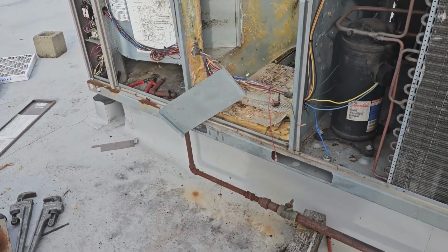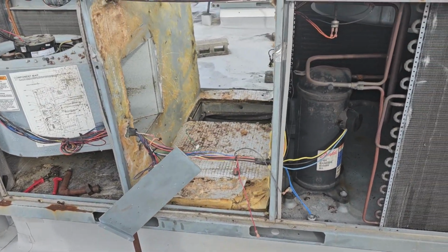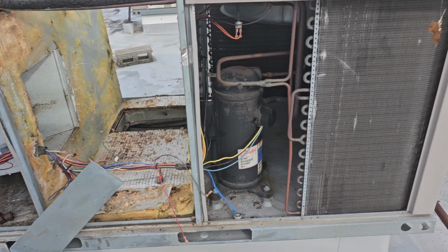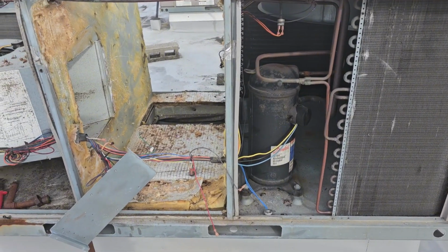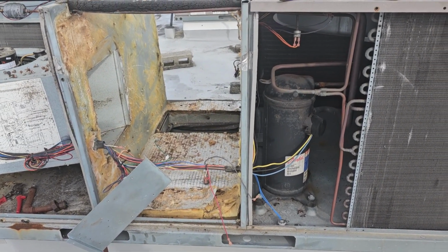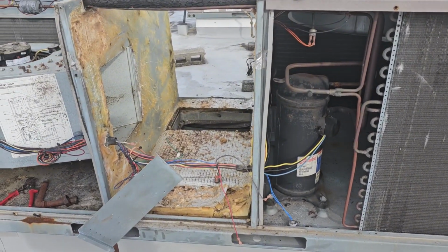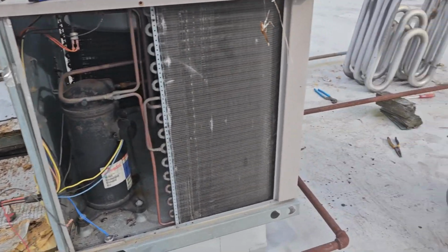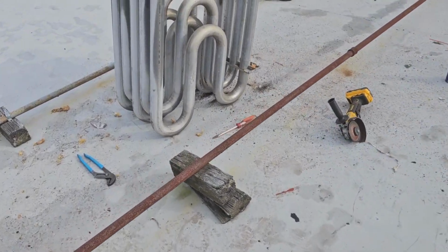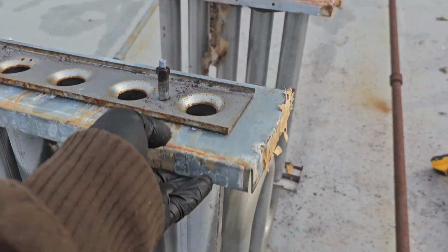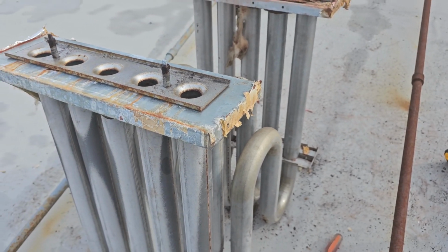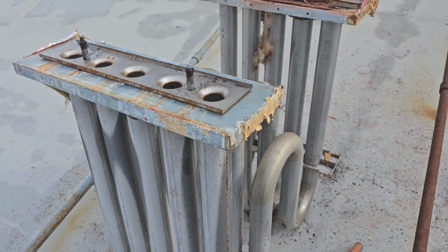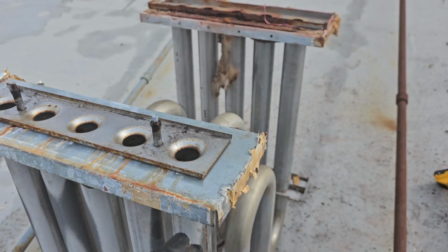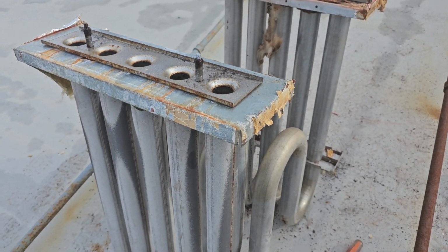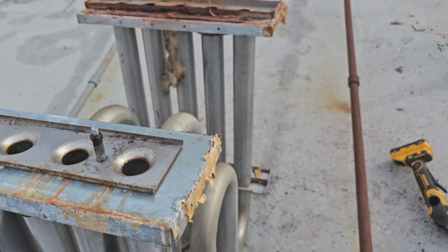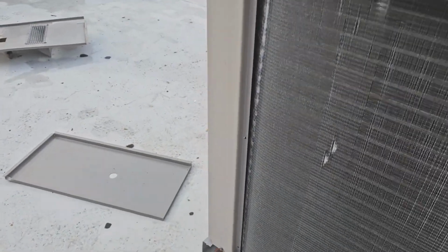Yeah, York units are almost not worth doing heat exchangers on, I'll be honest with you. If you could just replace the rooftop unit, you're better off. I mean, these heat exchangers are pretty heavy duty, not like Carrier heat exchangers where they only last about 8 years. I think these York heat exchangers last much longer, so by the time this heat exchanger is dead, it's probably time for a new rooftop.